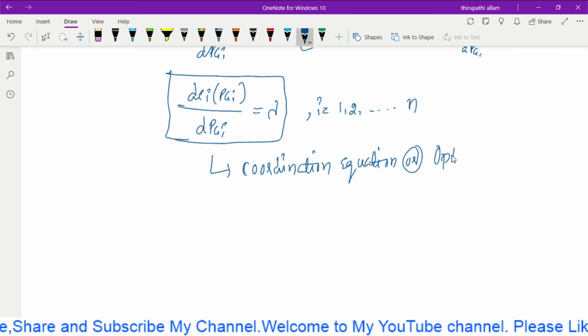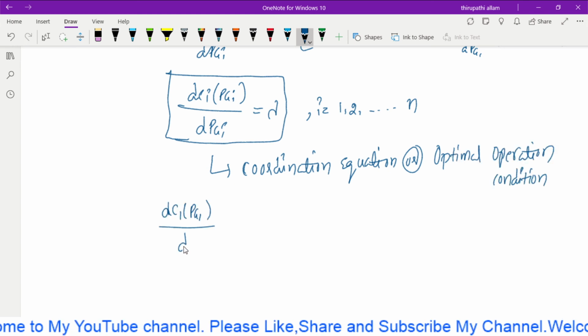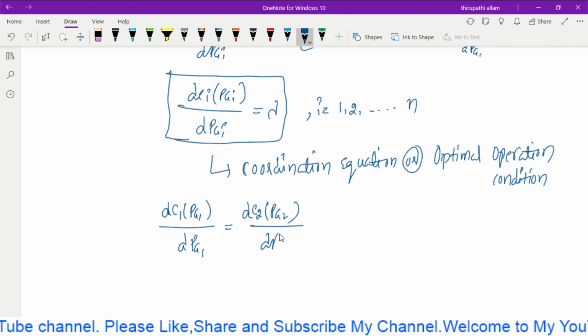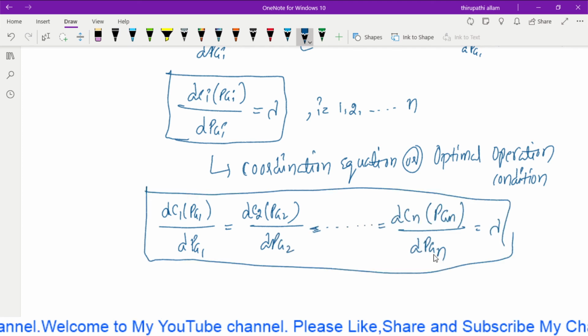Now here you can simplify. If it is i equal to 1, you get dC1 by dPG1 equal to dC2 by dPG2 equal to ... equal to dCn by dPGn equal to lambda. So the same equation is written for i equal to 1 and substituted. Now finally we can think that these are the coordination equations.